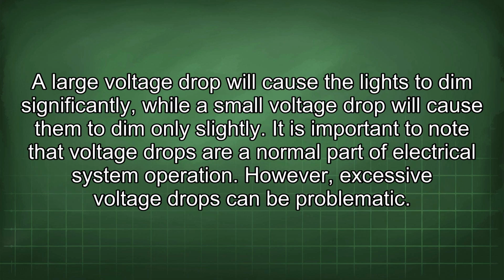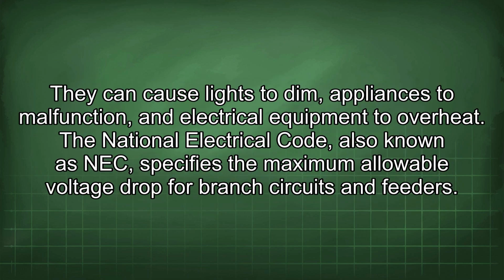A large voltage drop will cause the lights to dim significantly, while a small voltage drop will cause them to dim only slightly. It is important to note that voltage drops are a normal part of electrical system operation. However, excessive voltage drops can be problematic. They can cause lights to dim, appliances to malfunction, and electrical equipment to overheat. The National Electrical Code, also known as NEC, specifies the maximum allowable voltage drop for branch circuits and feeders.